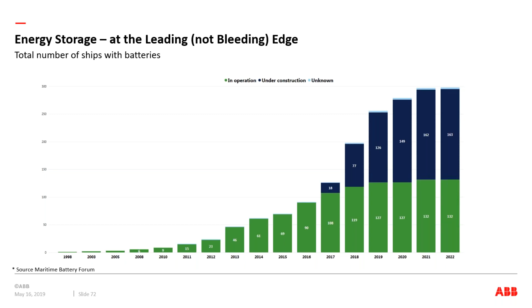The first is spinning reserve. If we think back to our case study mentioned a minute ago, the idea of not having to run engines, particularly multiple engines for redundancy purposes, and keep them at low load or idle during periods of low power demand, that can be a huge fuel savings right there. Typically that's done just to have for emergency purposes or to quickly respond when the vessel's in standby mode. But with batteries, first of all, they respond faster than any diesel can, and second, you don't necessarily need a big battery bank to make that happen. Batteries can respond quickly, and then you can transfer over to diesel generator power afterward if necessary. So there's a huge opportunity to save time when vessels are at low load, particularly for the spinning reserve opportunity.